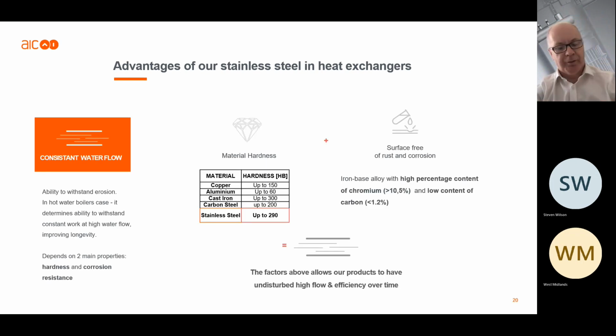And the hardness of stainless as well, it's a very hard alloy. Again, if you look on the chart here, it's measured in HB, which is 290 HB. Against aluminium, which is 60, it's 5 times harder material. And what that allows is consistent water flow. When you've got high velocity water going through the heat exchanger, it's much harder and can sustain that pressure, and it won't corrode or erode, for the other reasons that I said. So you have no breakage in the water flow at all. You get consistent water flow, and with consistent water flow, you get maximum heat transfer and no loss of efficiency through time.